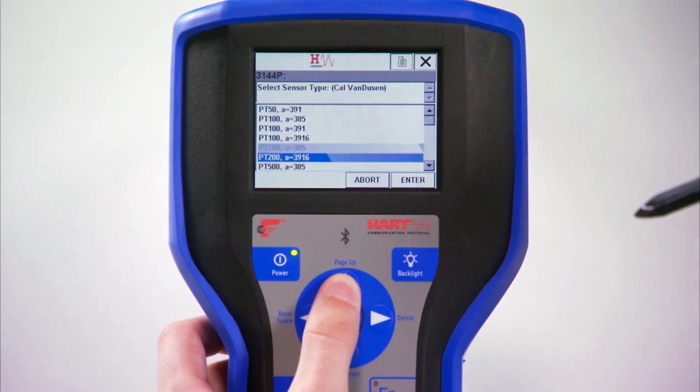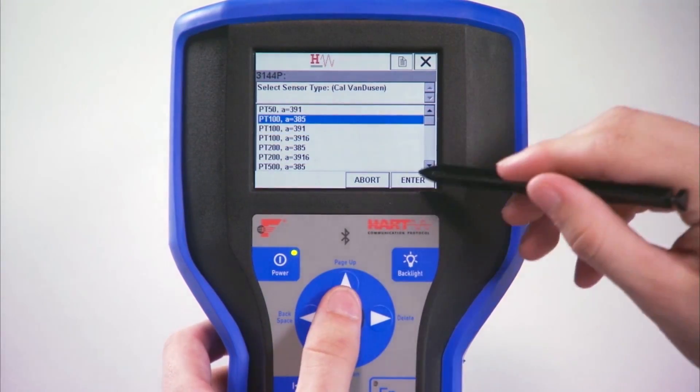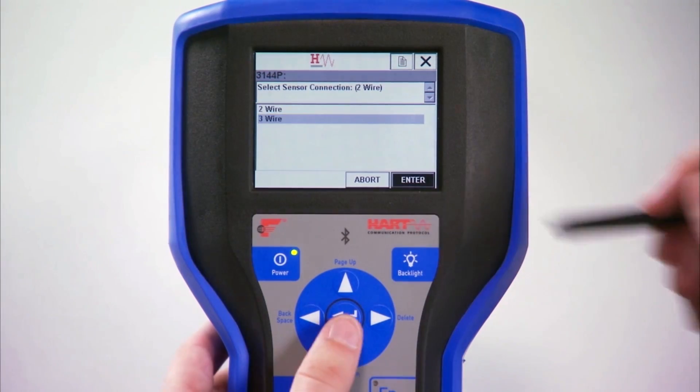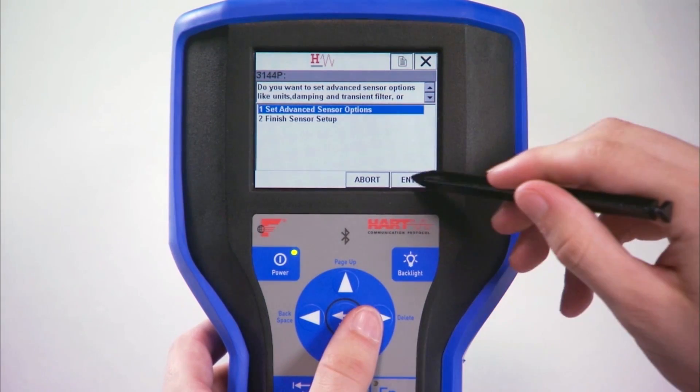Scroll through the list to find the sensor type of your attached sensor and press Enter. If you selected an RTD, choose the correct number of wires and press Enter. Press Enter again to continue the configuration.